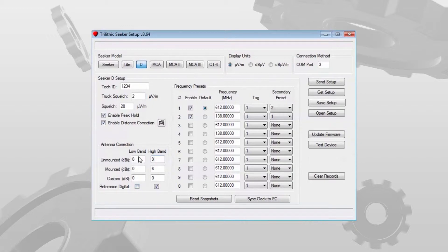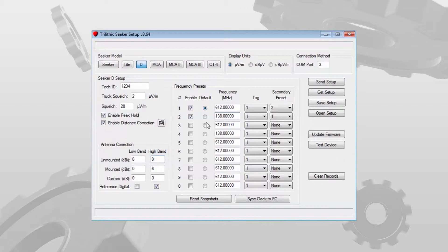In this case, for the low band, reference digital is not checked. So that tells me I have an adjacent analog channel to the 138 MHz carrier.